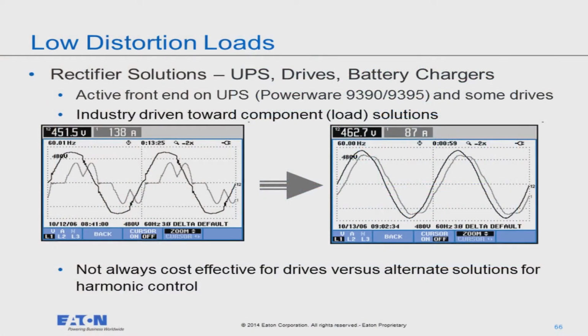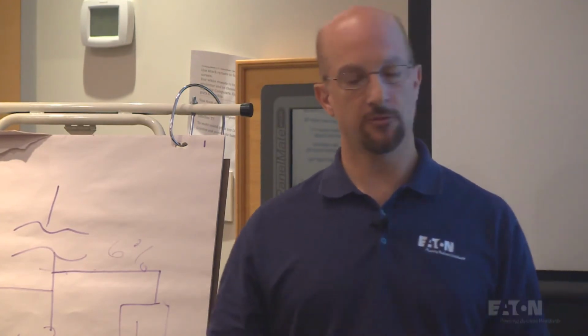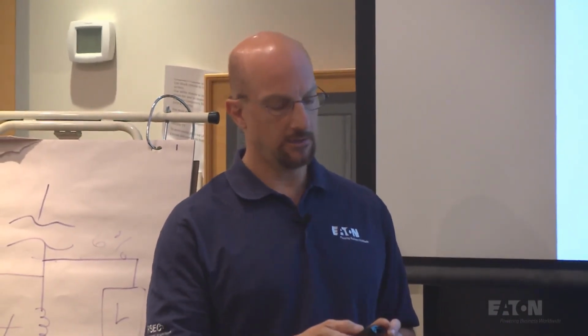Now, if you take that same thing and say, okay, should we do that with all our drives? Again, a very high percentage of the drives are 6 pulse drives. Now, instead of taking anything out, we're just adding additional costs. So that's where an active rectifier on a drive doesn't always make a lot of sense, because you're adding a lot of cost. It depends on the application, but going from 6 pulse to 12 pulse to 18 pulse, and then going to the next level really just depends on cost. And that's why, again, in the UPS or data center world, they get away with it.